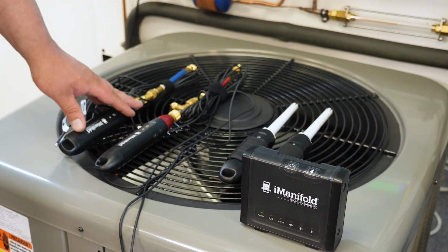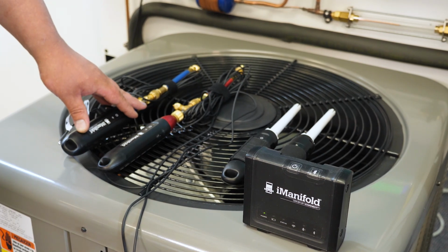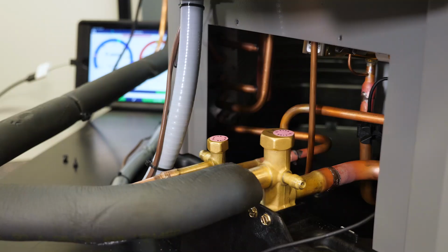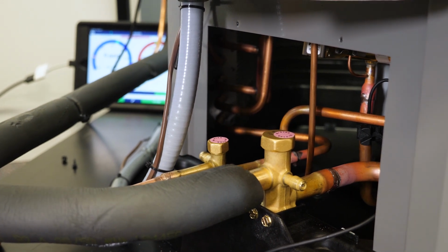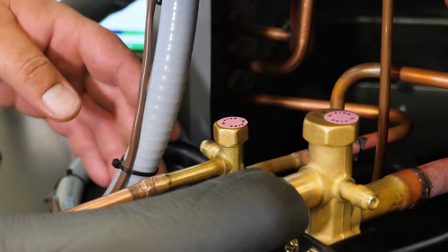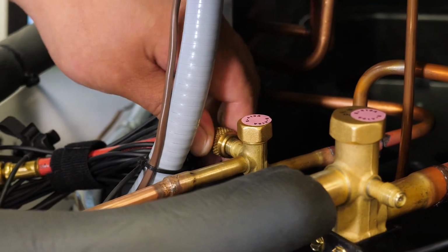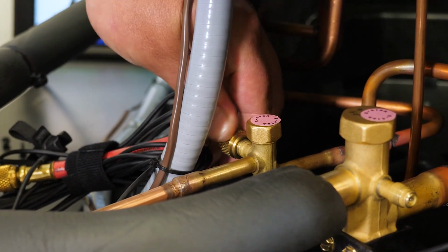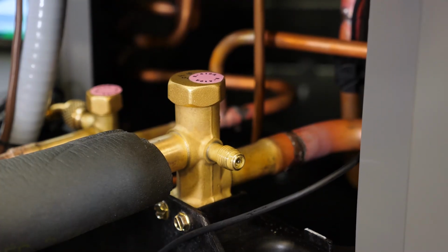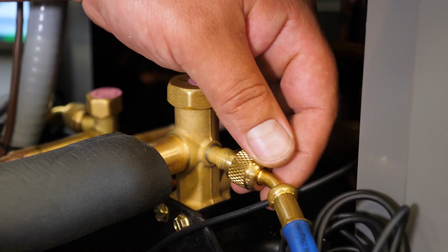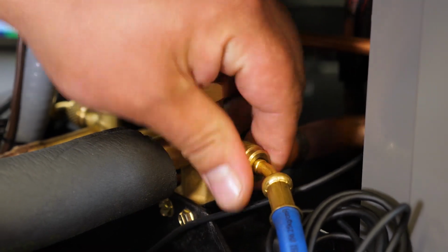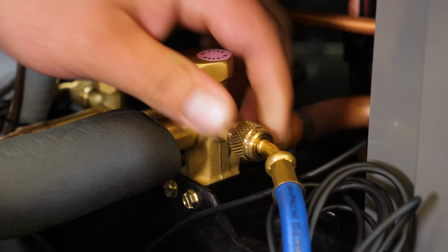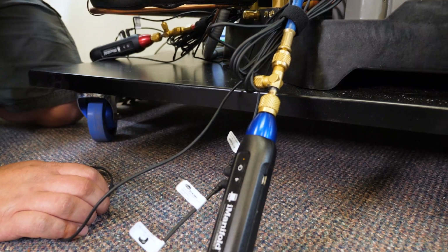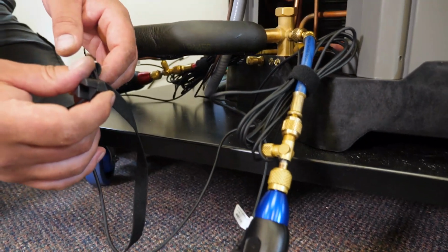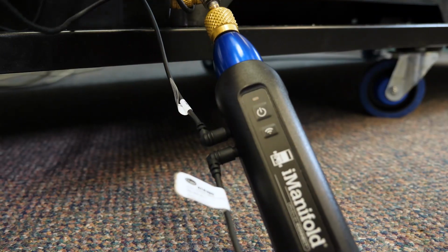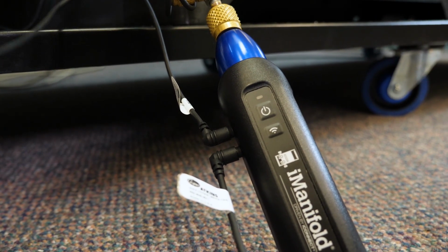So I'll go ahead and show you where we're going to hook these pressure probes up down to the access ports below. Okay, so here we have our liquid line access port and our suction line access port. I'll hook our high pressure probe up to the liquid line. Now I'll hook up the low pressure probe up to the suction port. So on my T1 port on my low pressure probe, I have that going to my pipe strap thermistor going to my suction line. On my T2 port, I have my outdoor air thermistor.